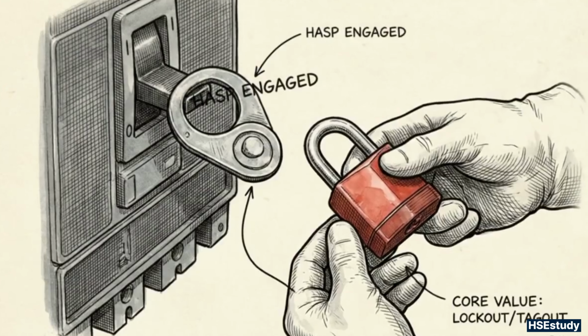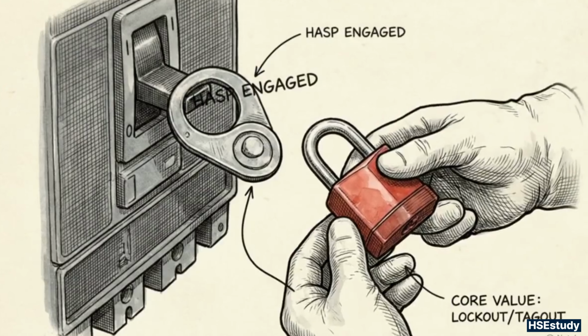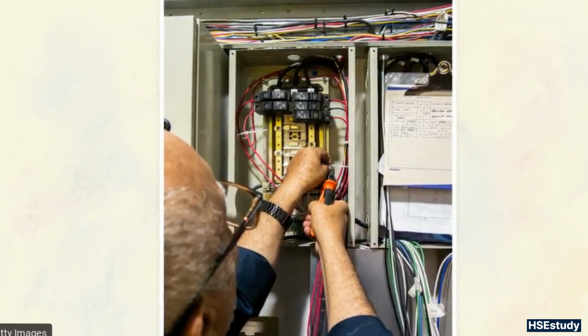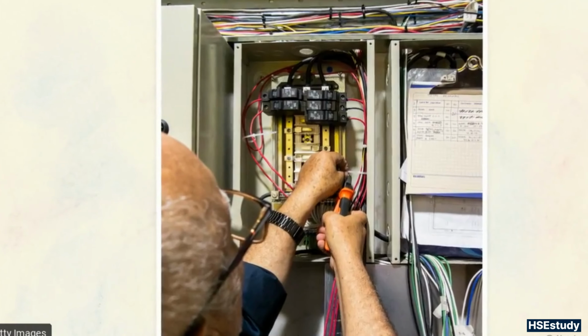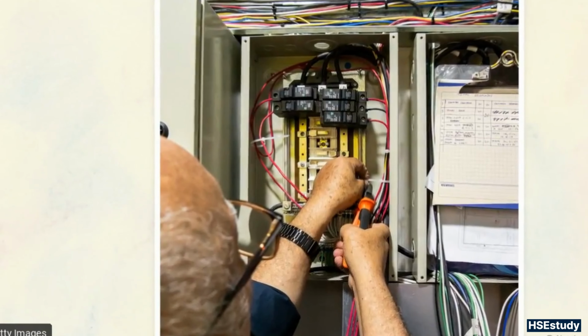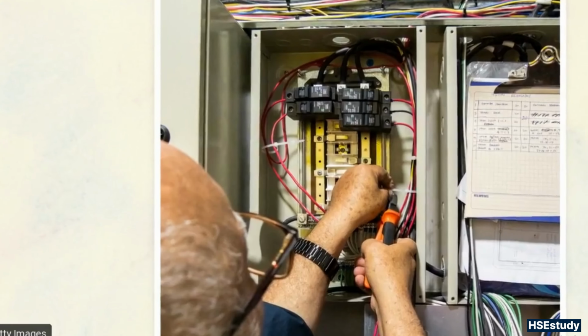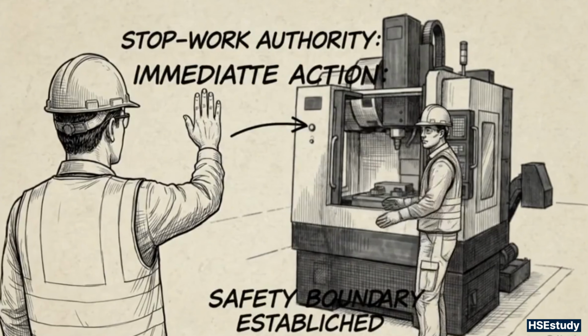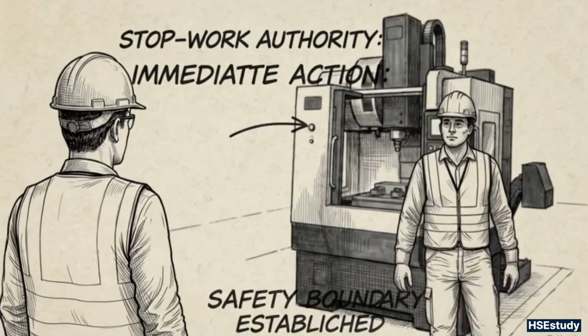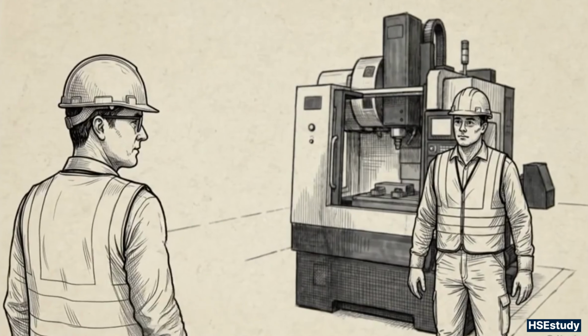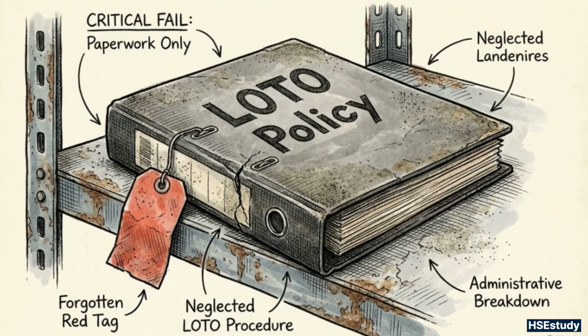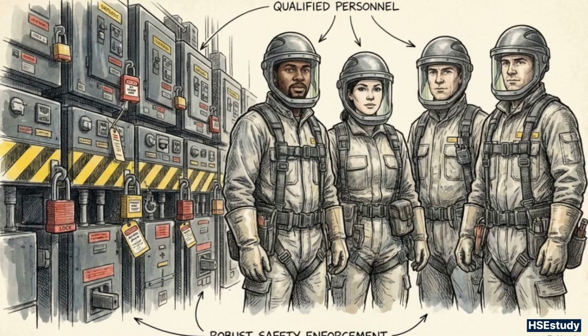Organizations must shift from treating compliance as an administrative goal to operating with safety as an uncompromising core value. Facilities require a strict de-energization first culture. Any energized work must be treated as a high-risk exception that demands multi-level authorization and justification. This requires real-time verification audits of LOTO procedures and empowering every worker on the floor with absolute stop-work authority. Paperwork alone will never stop a machine from energizing. Only a robust, consistently enforced LOTO system, backed by qualified personnel training, can prevent these tragedies.